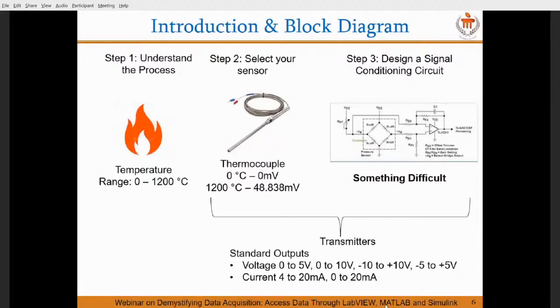Suppose I need a 0 to 1200 degree centigrade measurement. My transmitter is going to be calibrated to give me either 0 to 5 volts or 4-20 milliamps. Usually the current standard is normally used in industry, so we'll go with 4-20 milliamps. There are other standards available too - you may go bipolar as -10 to +10, -5 to +5, or 0 to 10 volt are some of the voltage standards. But if you look at the current standard, it is going to be 4-20 milliamps and 0 to 20 milliamps.